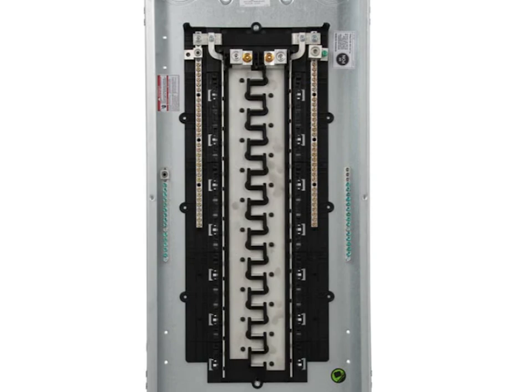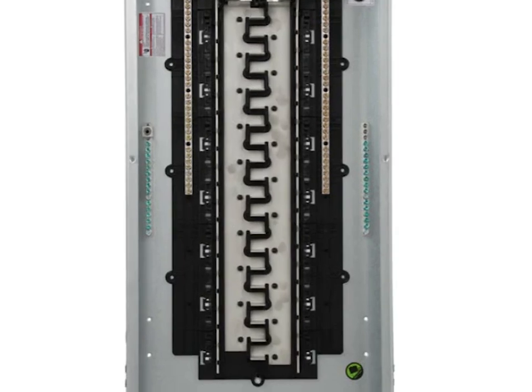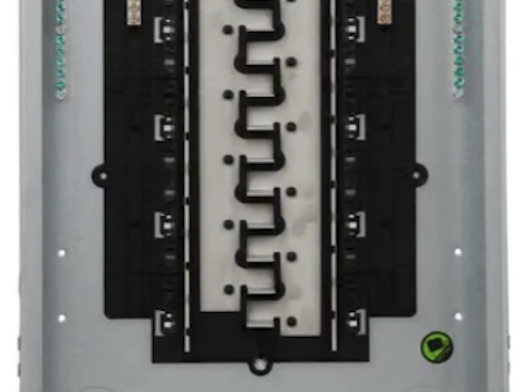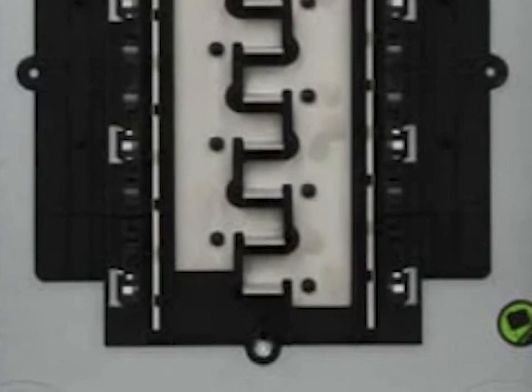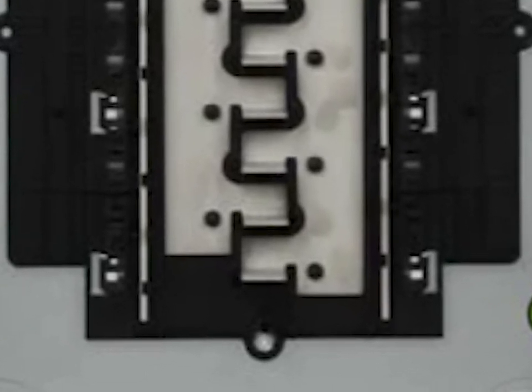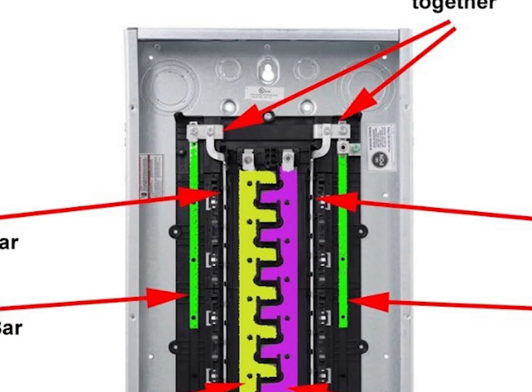Blades. The power bars each have blades that the end of the circuit breaker clips into. Remember, these bars are 120 volts each. Circuit breakers across from each other plug into the same blade. One uses the left half, the other the right. These opposite circuit breakers are powered by the same phase of power. In the drawing, the top two circuit breakers would be on the yellow power bar. The next set of two circuit breakers would be on the purple power bar.